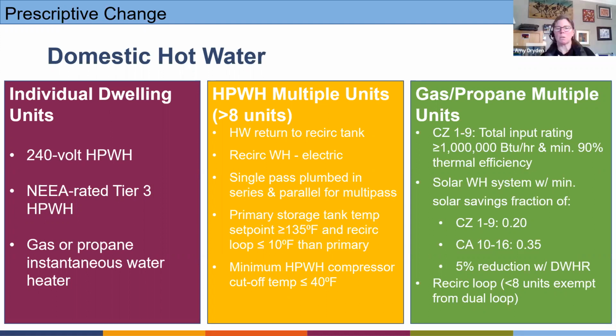systems. Solar water heating systems have a minimum solar fraction savings by climate zone. You can see listed out there. If I include a drain water heat recovery, I can get a 5% reduction in my solar fraction. And then the one piece that's called out that does differentiate by number of units is my recirc loop. I don't have to have a dual recirc loop if I have less than 8 units.